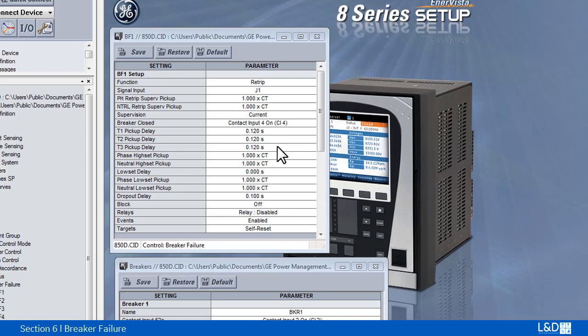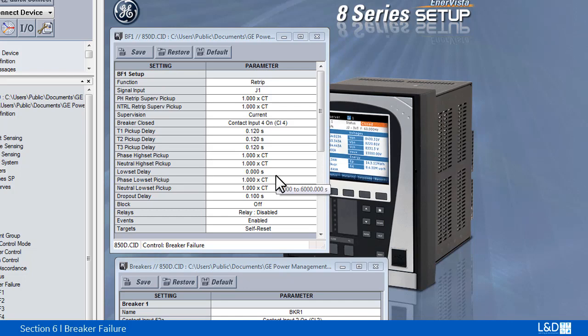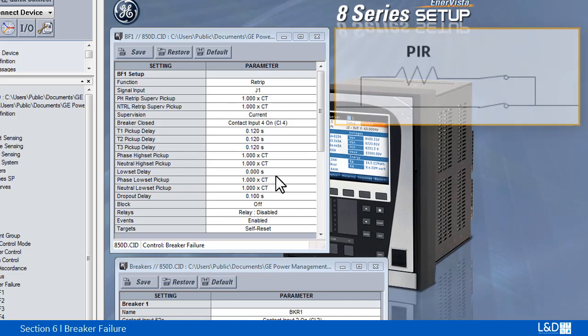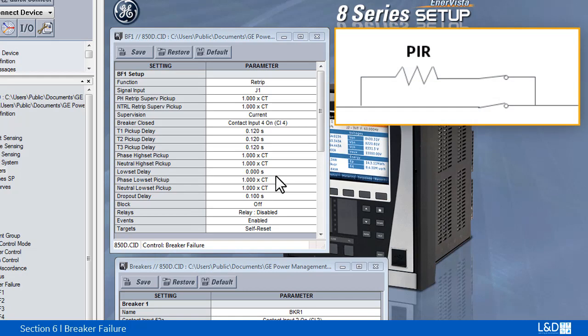Timer 1 and 2 logic provide two levels of current supervision: high set and low set. This allows the supervision level to change, for example, from a current which flows before the breaker inserts a pre-insertion resistor PIR into the faulted circuit to a lower level after resistor insertion.